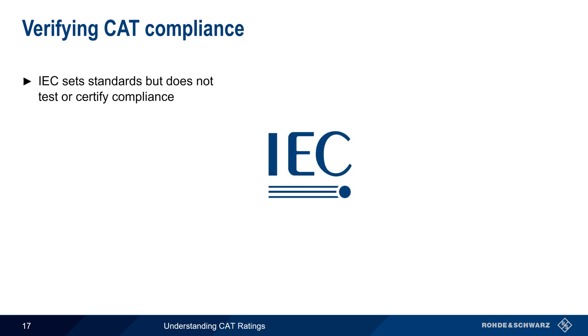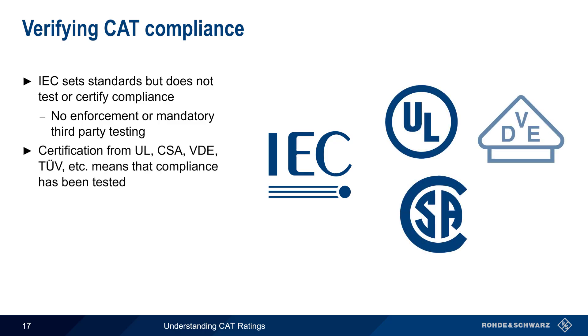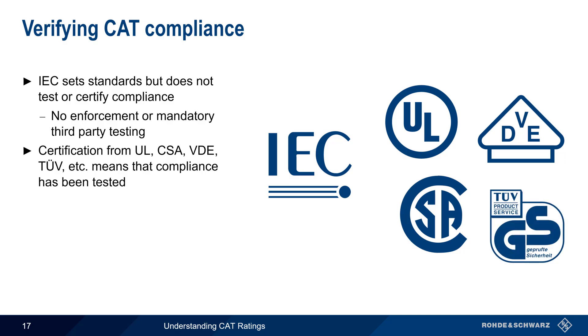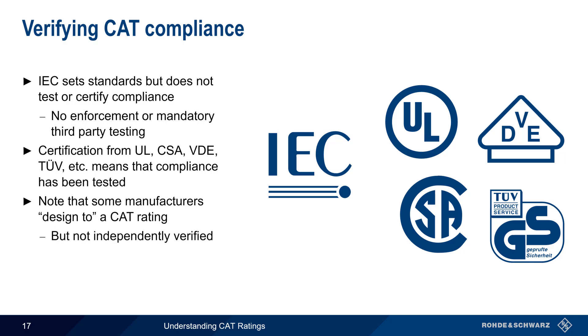Although the IEC defines CAT ratings, it's important to keep in mind that the IEC does not enforce these standards or require mandatory third-party testing to ensure compliance. Various international electrical safety organizations, such as UL, CSA, VDE, etc., do however certify electrical devices, and this certification usually includes verification of the given CAT rating. Note that although some manufacturers state that they design to a given CAT rating, this does not necessarily mean that an instrument's CAT rating has been independently verified.